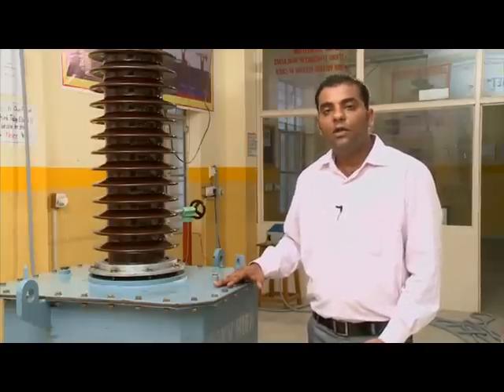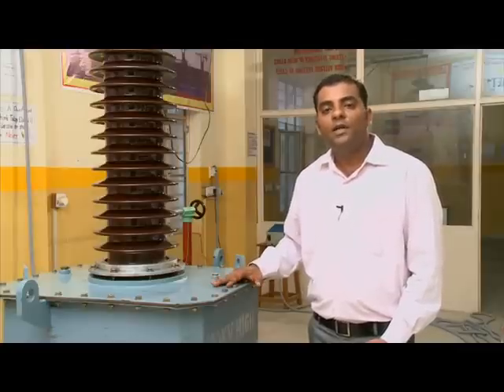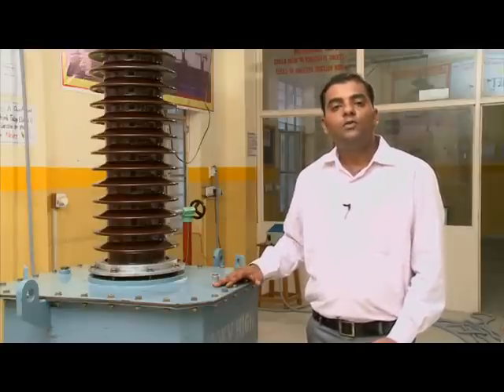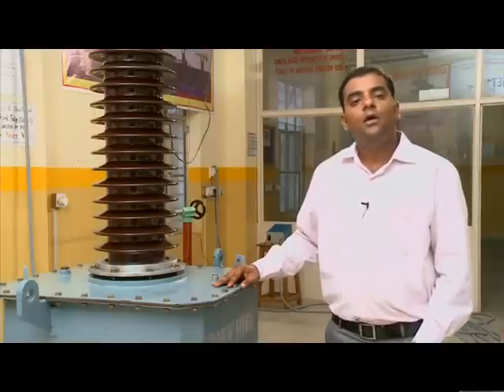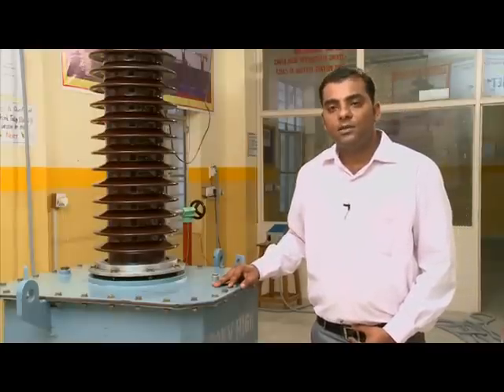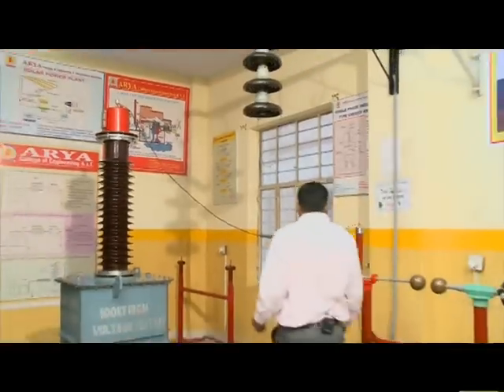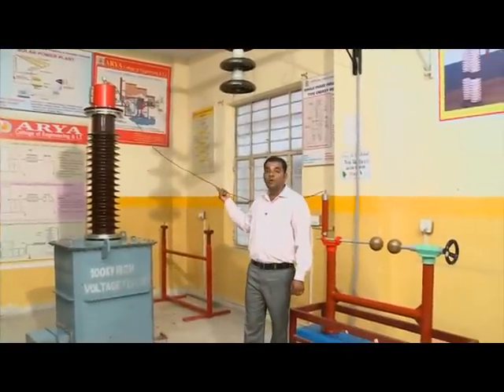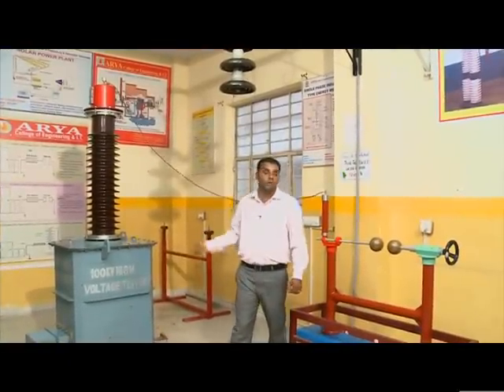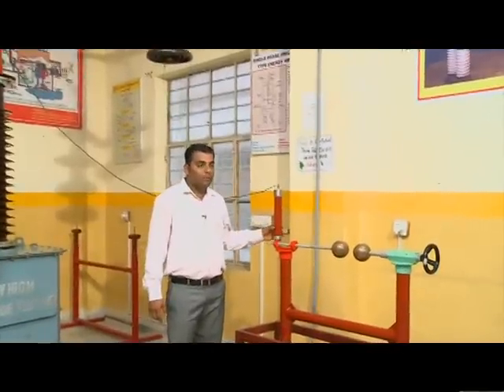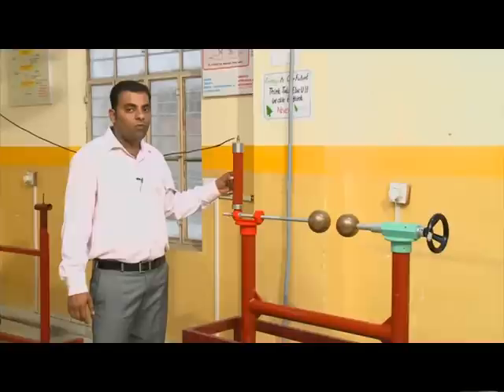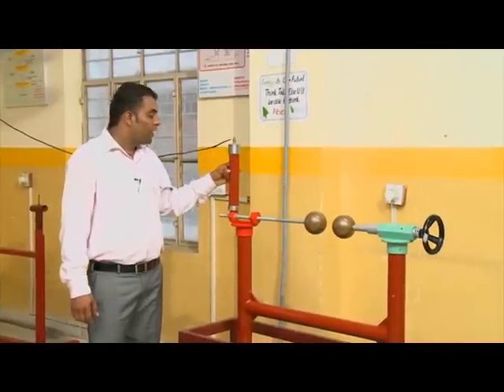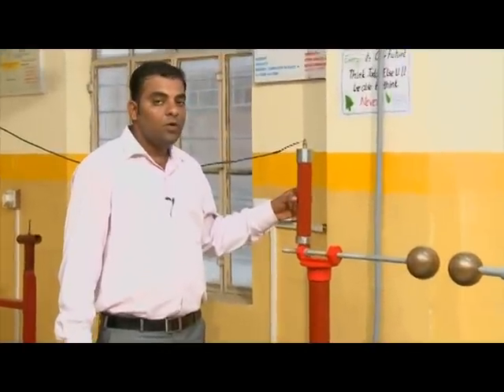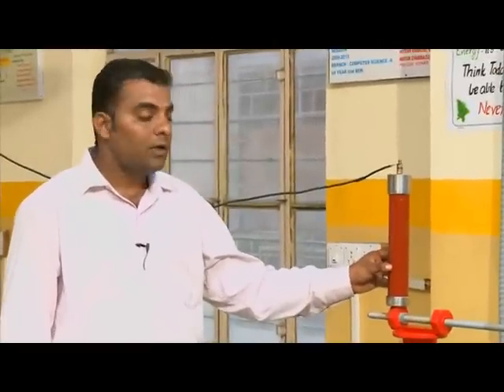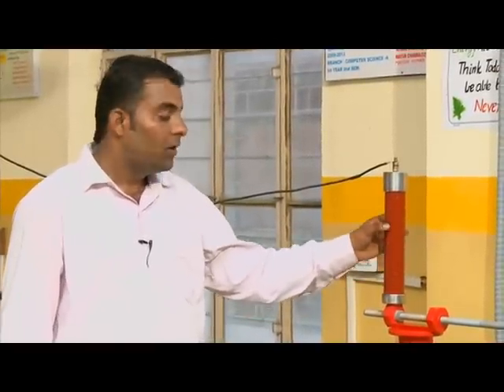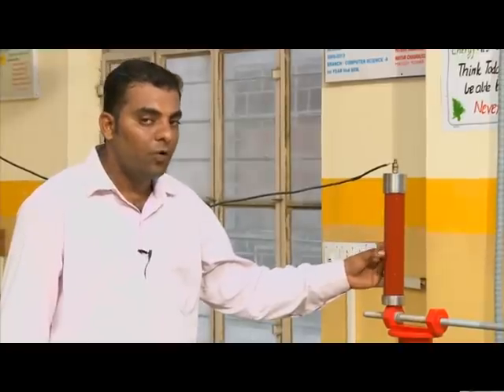By using this transformer, we supply the high voltage to the Rhodes sphere gap method. By using the Rhodes sphere gap method, we can analyze the peak value of the transmitted voltage. It is the output supply of the transformer which is connected to the Rhodes sphere gap method panel with the help of a water resistor. We are using this water resistor to reduce the breakdown current, and it suppresses the unwanted oscillation of the input voltage source.